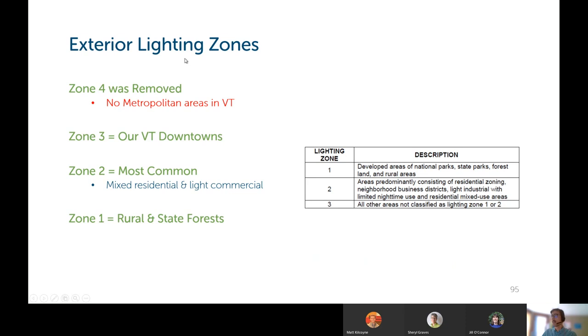All right, exterior lighting. You need to assign the exterior lighting zone that the project is occurring in. For this code, zone 4 was removed entirely, which is good because it never applied to Vermont. That's only the largest metropolitan areas, which Vermont does not have any of. Zone 3 is our downtowns in Vermont, areas with the highest amount of exterior lighting. Zone 2 is the most common around Vermont, which is other villages, mixed industrial and light commercial usages going on. And zone 1 are pretty rural, undeveloped areas, national parks, state parks, and forest lands. Some ski areas and their buildings are applicable to zone 1 lighting requirements.